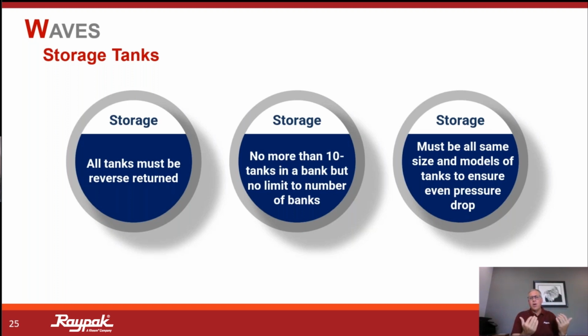We have even pressure drop, but then there are, again, no limit to the number of banks of 10 storage tanks. That would be a fairly sizable job. I don't know how often, if at all, that will come into play, but that is one of the guidelines that is worth noting in that manual. All storage tanks must be the same size so that we have that even drawdown, that even pressure drop.